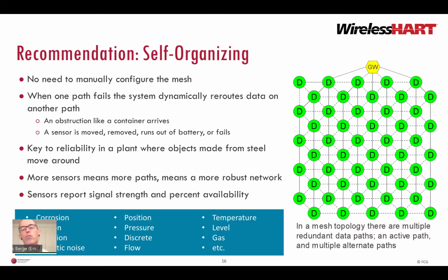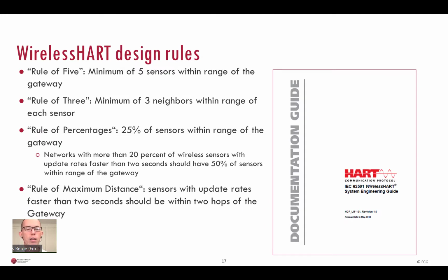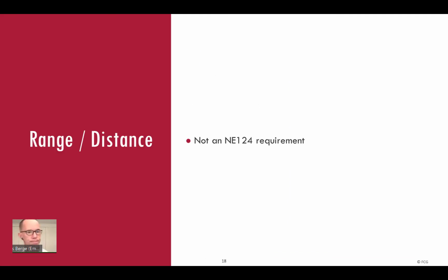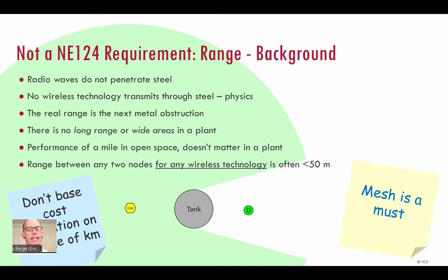But it's important to follow the WirelessHART design installation rules. The more sensors there are in a mesh network, the more possible paths there are between these sensors, and therefore the more robust the mesh network becomes. That is because a WirelessHART network is shared between many kinds of sensors for various use cases, you get a strong mesh of connections. Other wireless sensor network technologies without mesh topology or which are not self-organizing cannot achieve the same reliability.